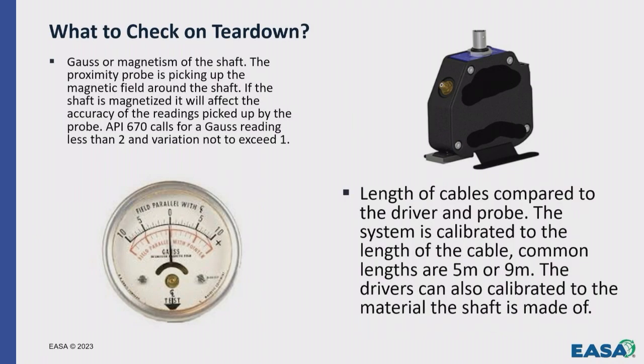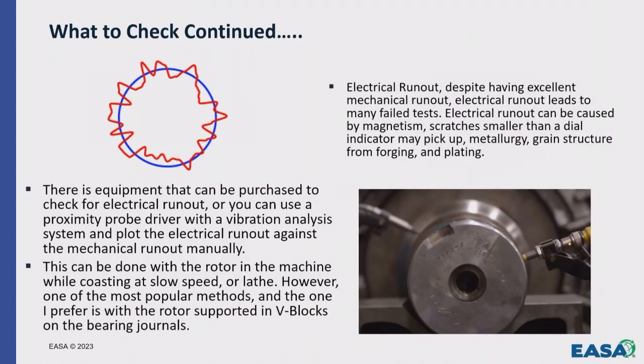What do you want to check on teardown? You want to check for Gauss or magnetism of the shaft. That will cause erroneous readings. And then look at the length of the cables compared to the driver. That's a picture of a sample driver. But on the side of that driver, it's going to say usually a 5 or a 9 meter. Those are the most common lengths. And make sure the cables match that. They're calibrated sets. And a lot of times people mix and match and don't pay attention, and that can affect your accuracy a little bit. But if your magnetism is high in the shaft, you will have false readings.